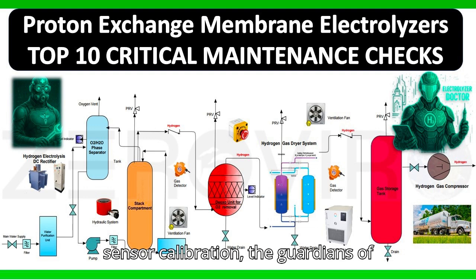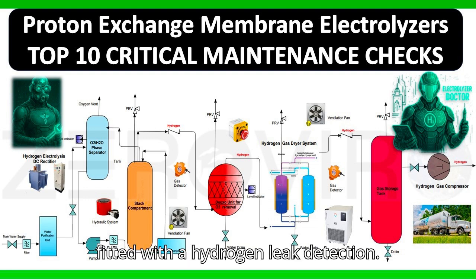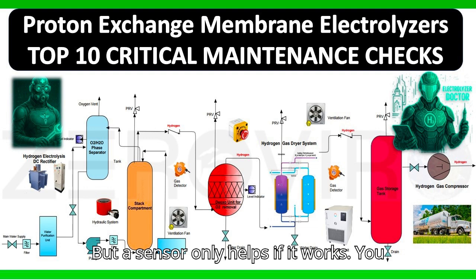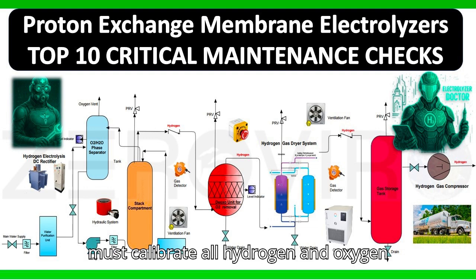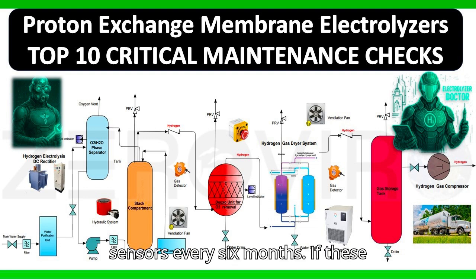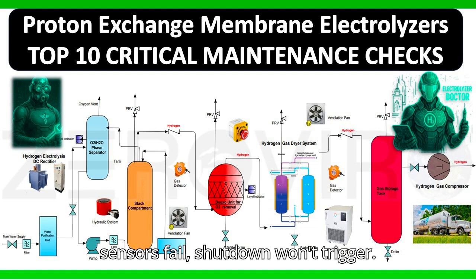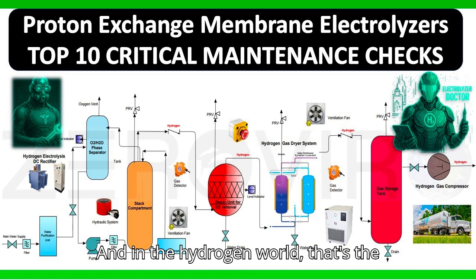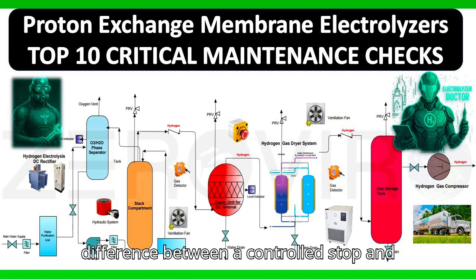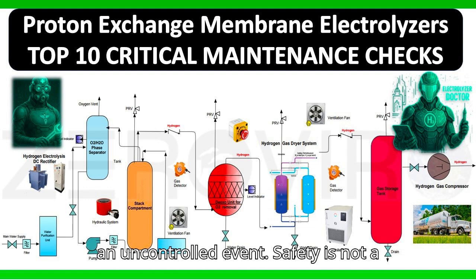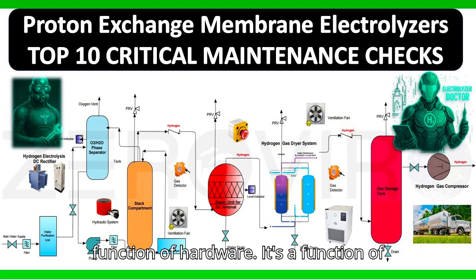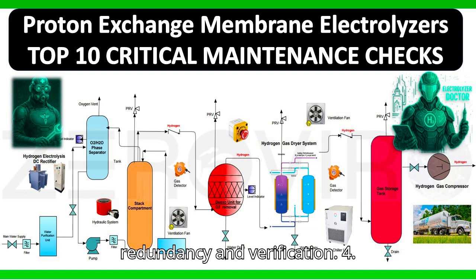3. Gas sensor calibration, the guardians of safety. Every modern electrolyzer is fitted with hydrogen leak detection, but a sensor only helps if it works. You must calibrate all hydrogen and oxygen sensors every 6 months. If these sensors fail, shutdown won't trigger. And in the hydrogen world, that's the difference between a controlled stop and an uncontrolled event. Safety is not a function of hardware. It's a function of redundancy and verification.